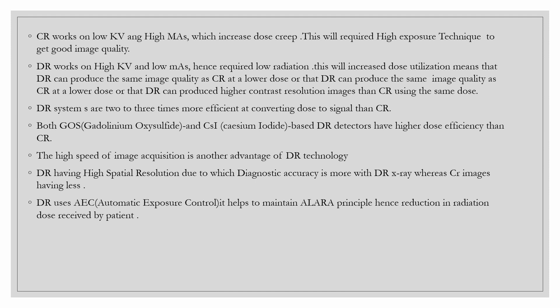DR systems are two to three times more efficient at converting dose to signal than CR. Both Gadolinium Oxysulfide (Gd2O2S) and Cesium Iodide (CsI) based detectors have higher dose efficiency than CR. In DR, the high speed of image acquisition is another advantage, and detectors have high spatial resolution, resulting in greater diagnostic accuracy than CR.